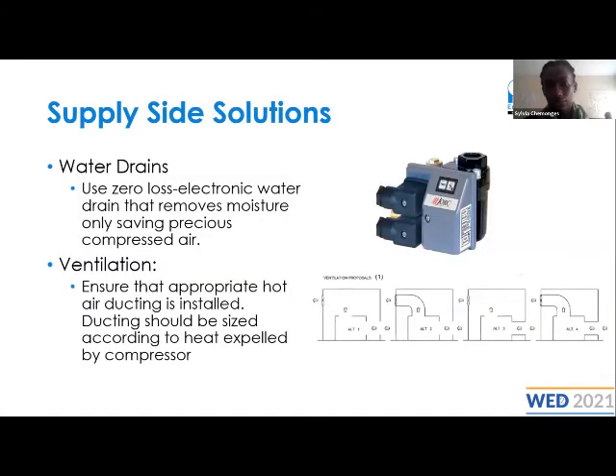From there, another thing that can help us is to incorporate water drains. We had mentioned the issue of manual draining. So you'll go to most industries and meet people draining condensate from their receivers manually. The issue with that is as you drain, you lose compressed air. Also, the number of times you drain sometimes depends, because the amount of condensate in the air varies with the humidity and it varies from month to month.